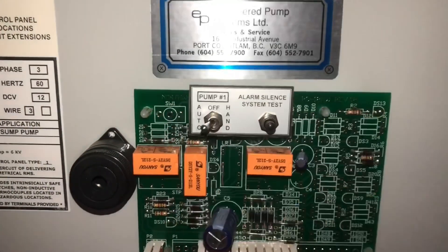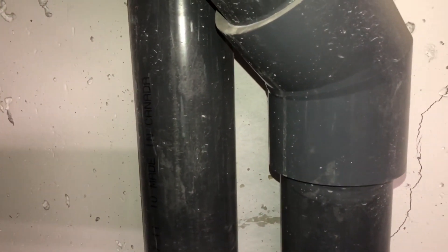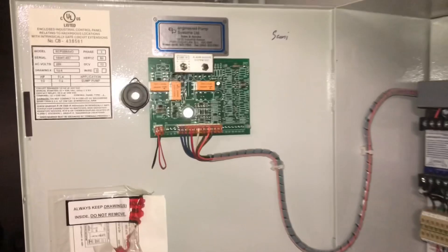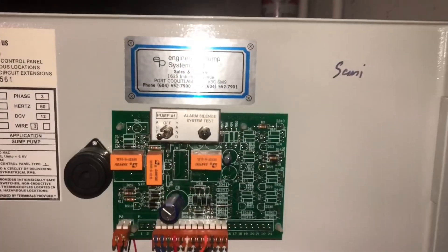This one here I've turned on, and you can actually hear water coming up through these pipes now. That means there was water in the system that wasn't going to get pumped out because somebody had shut off the pump. They should have left it in the auto position. So much for a vandal-proof system.